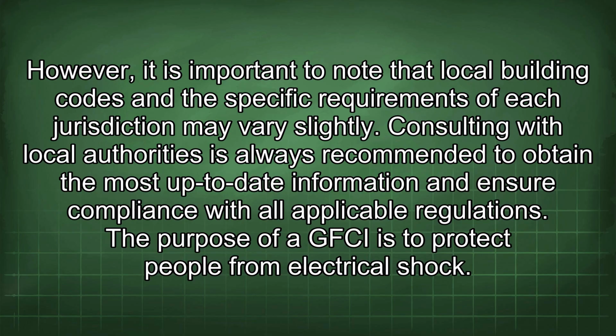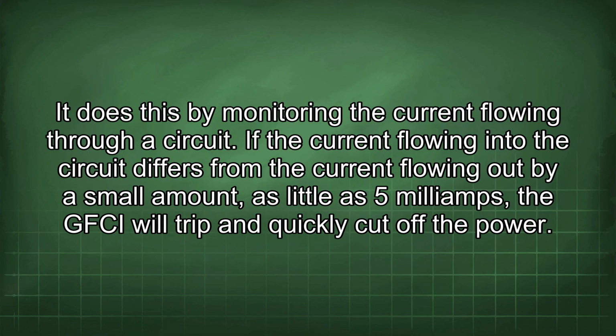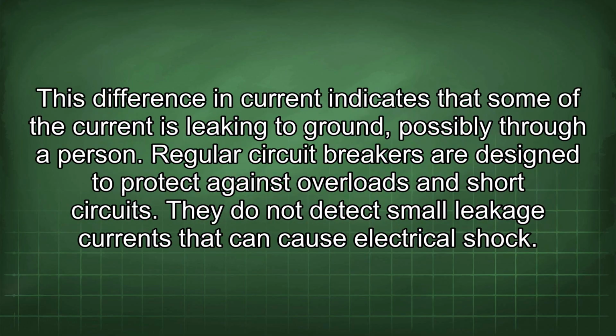The purpose of a GFCI is to protect people from electrical shock. It does this by monitoring the current flowing through a circuit. If the current flowing into the circuit differs from the current flowing out by a small amount, as little as 5 milliamps, the GFCI will trip and quickly cut off the power. This difference in current indicates that some of the current is leaking to ground, possibly through a person.